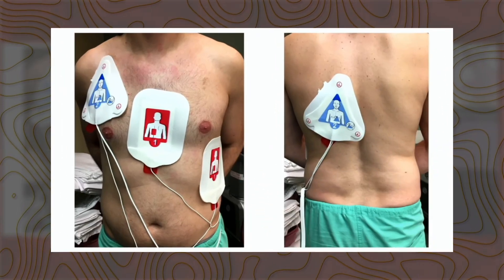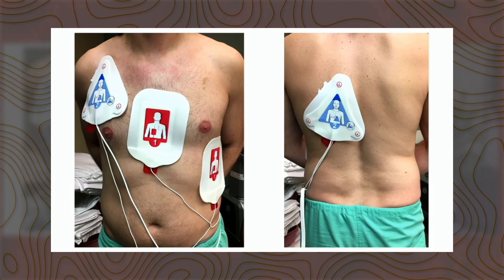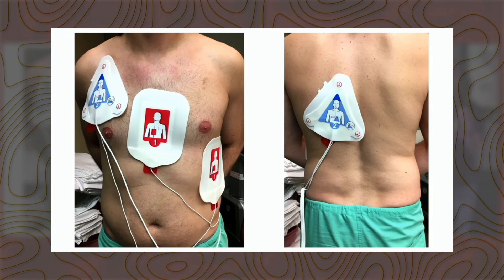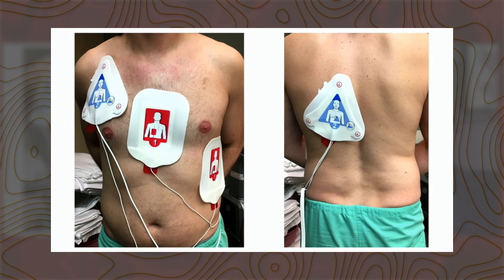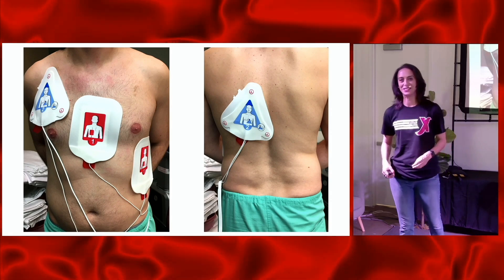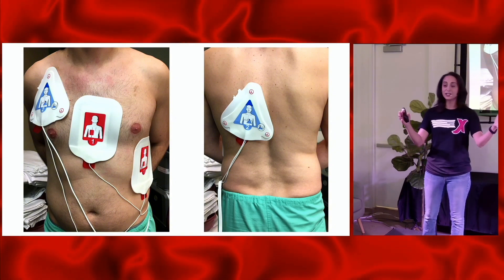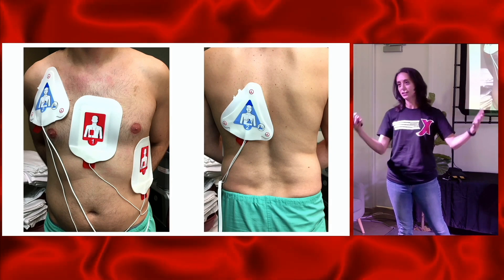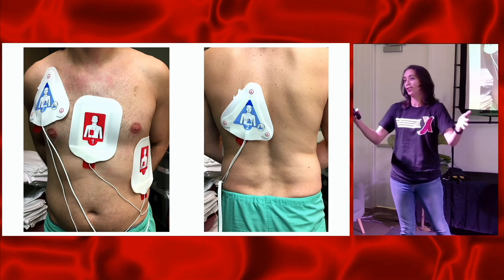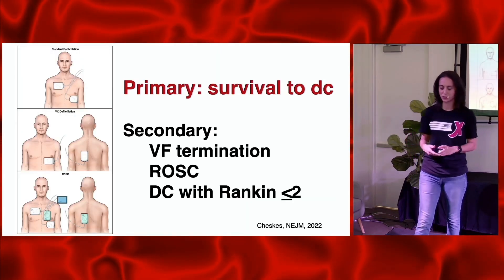I like to show this picture. I asked my co-workers to take a photo showing what all these pads look like. I blurred his face so nobody would know who it is, but I just want you to see how much real estate this takes to put these four pads on the patient. They actually sent me the photo with two of the pads in the wrong spot, but I'm still going to use it. You can see it takes a lot of real estate on a patient's chest — and this is a pretty big, robust guy. In a smaller, 50-kilo woman, this might be kind of challenging.